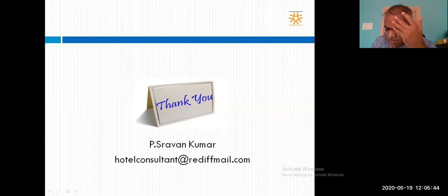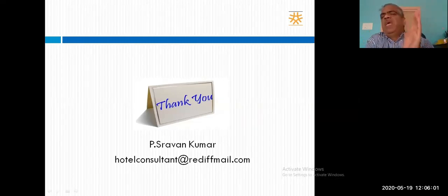I will leave this to Mr. Anmol Prabhu to answer. But by and large, for a common multi-cuisine standalone restaurant, in peak times, or if you have a banquet hall attached, we look at anywhere up to 30 ACPH. In lean times, we look at 20 ACPH. So an adjustment between 20 and 30 ACPH should be sufficient - you don't need more, and you can't work with less. Always maintain negative pressure in the kitchen so that front air isn't coming in and aromas aren't getting into the restaurant.